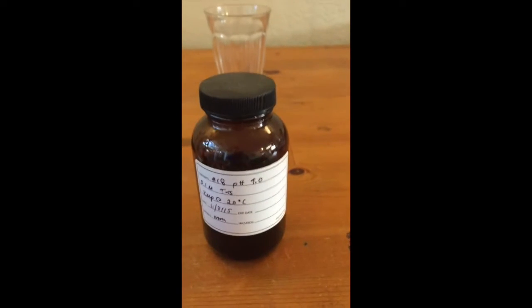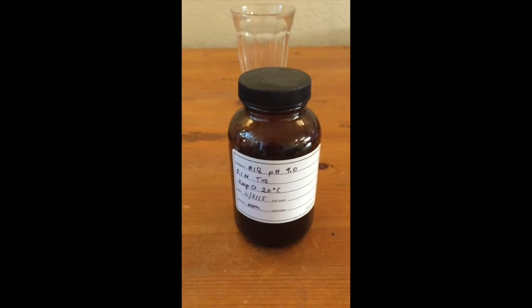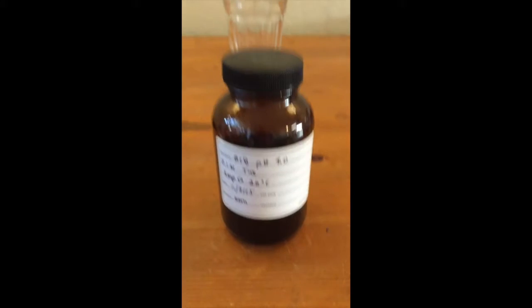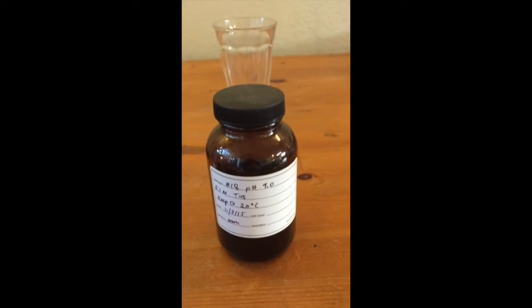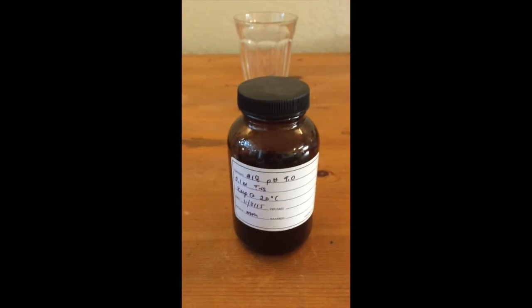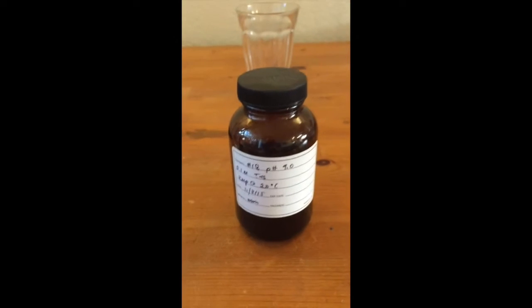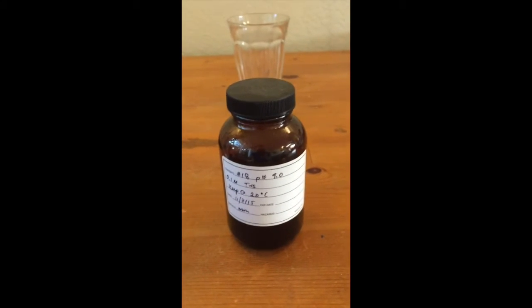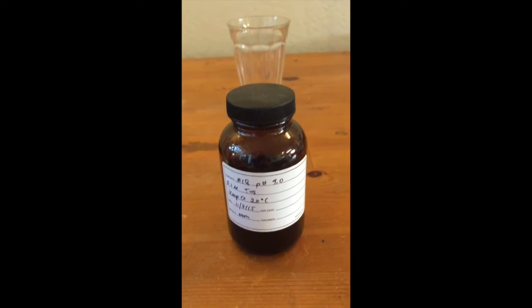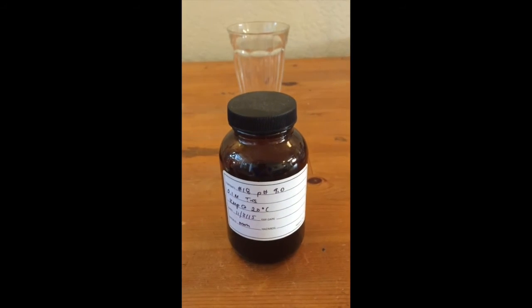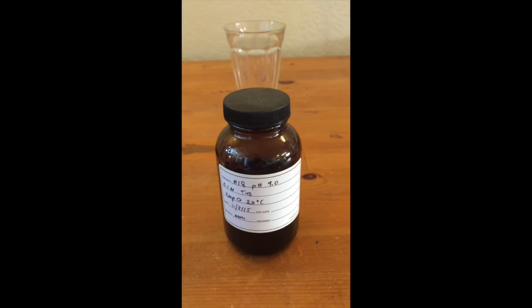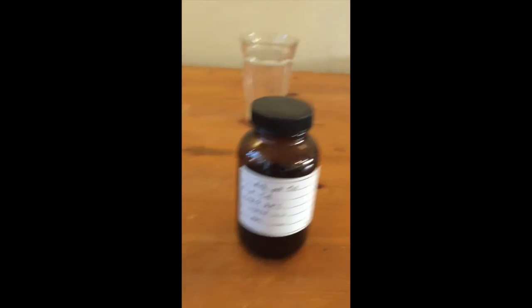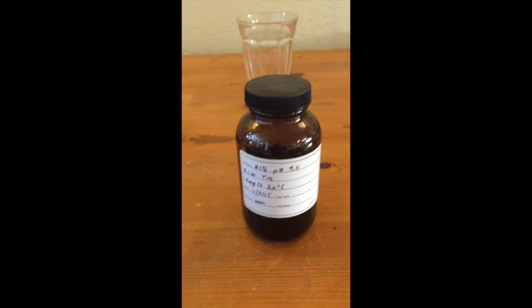You'll do the same thing for that higher pH. Unlike the 4.0, you don't have to use a set pH solution. You can use a 9.0 like we have here. You can use a 7.0, which is very common. You can use the water in your system, or you can just use tap water. If you're using not an established buffer solution where you know the pH, you need to read that pH with an independent probe that you trust and be able to enter that onto the database, which I'll show you how to do in a sec.